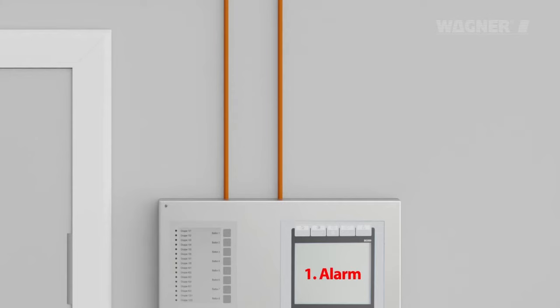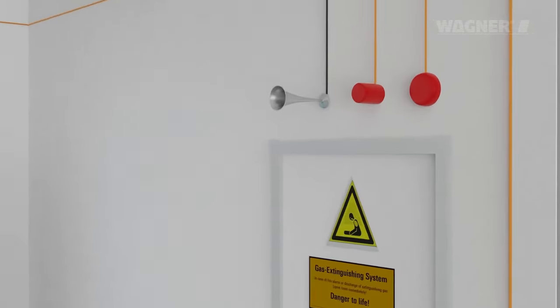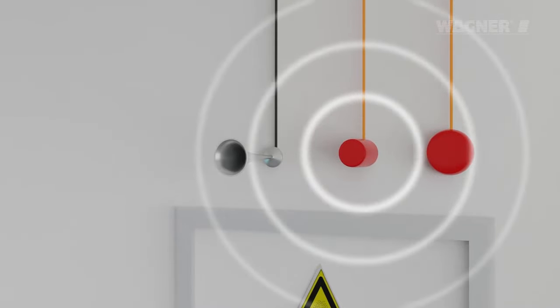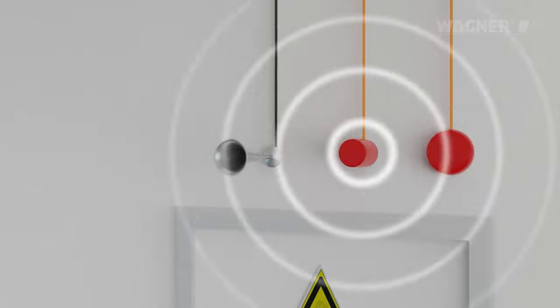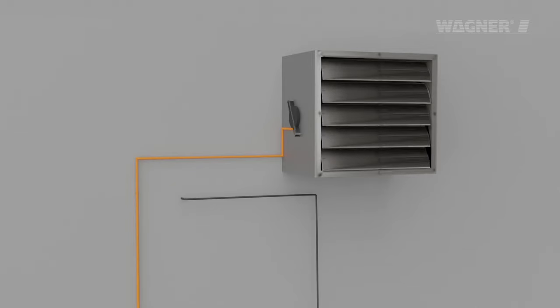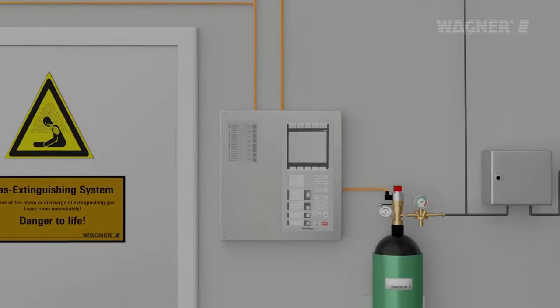With the first alarm signal, an acoustic alarm signal is automatically emitted and the fire damper is closed, thus interrupting the supply of fresh air.